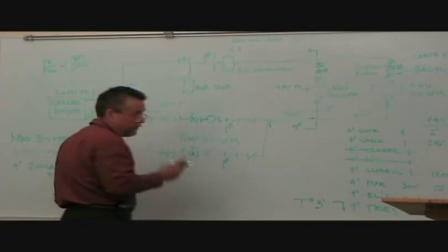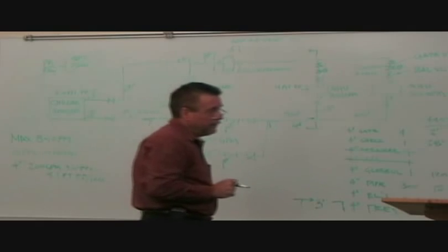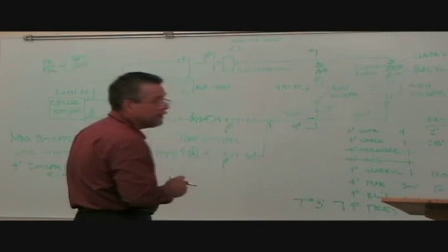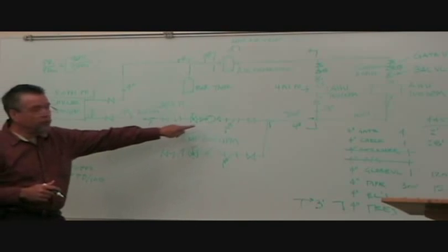One thing we didn't add in here, there's probably reducers right here. They'll have some effect on the pressure drop, but negligible. So there's my pump. Question, why would you put the reducers in there? Well, for a 200 gallon a minute pump, it's probably a 2-inch or 2.5-inch connection. I've got a 4-inch line. I don't know that for a fact, but I know that a 4-inch pump will probably do 500 or 600 gallons a minute. It's just whatever size the pump ends up being, 2, 2.5. Oh, okay, I see, because you have a pump. It's just the connection size. Okay, I got you.